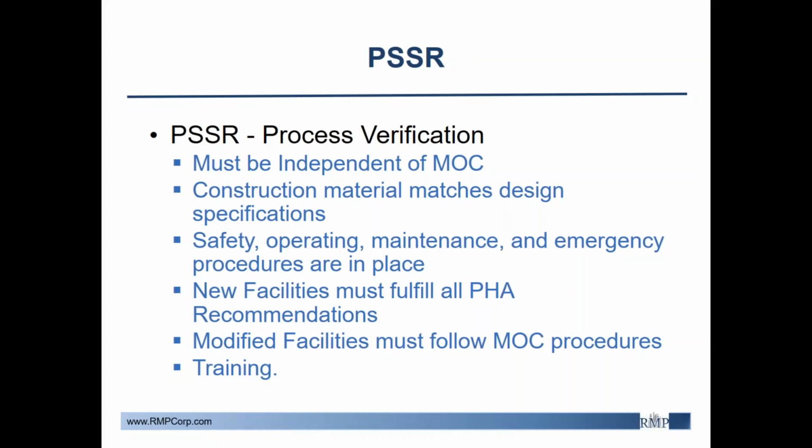You've updated your safety, operating, maintenance, emergency procedures as you said you would have, right? And that those procedures exist before you start up, and then that operators have been trained on those procedures, right? So you should be able to see that there have been training record forms, and then that a safety review has been done if one's required, and then you should be able to evaluate to see have the recommendations been taken care of as they needed to be, have they all been addressed, have they been closed out. All of this should be done before you start up, exactly as the name implies.